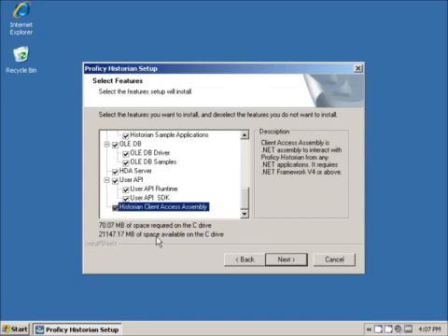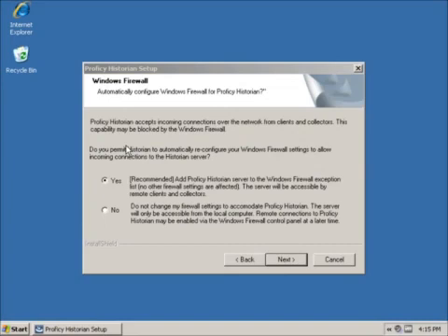Once we have selected the appropriate options, click Next to proceed. Historian can automatically add itself to the allowed programs for the Windows firewall, and this is recommended. Historian uses TCP port 14000 for its network communications, and is normally in the blocked range of firewalls.